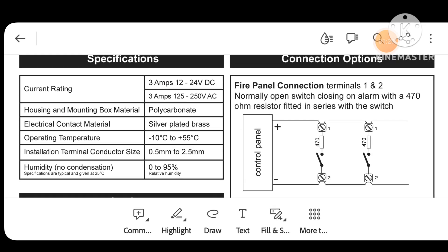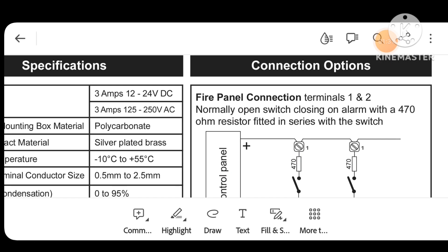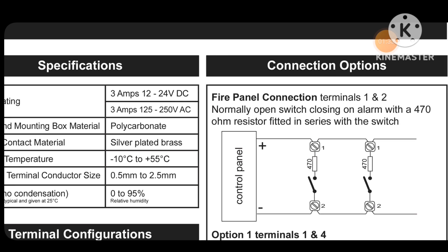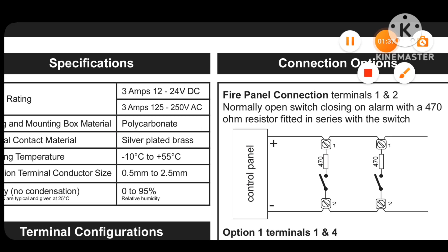Here we have connection options. Fire panel connection terminals 1 and 2 — how we connect: normally open switch closing on alarm, which uses a 470 ohm resistor for some systems and a 140 ohm resistor for other systems.